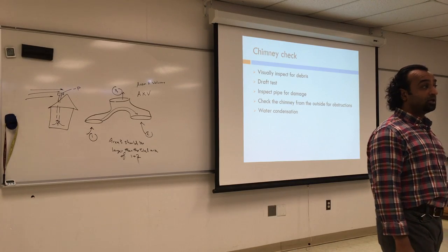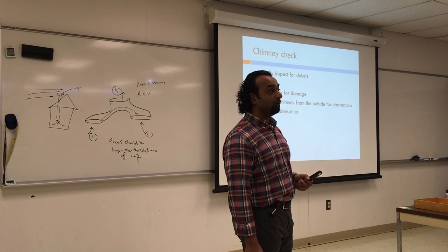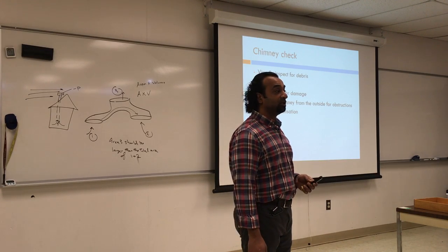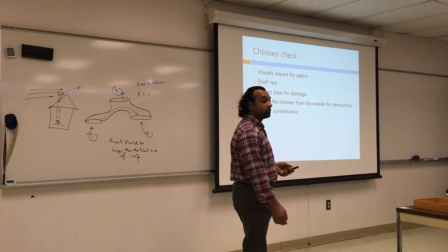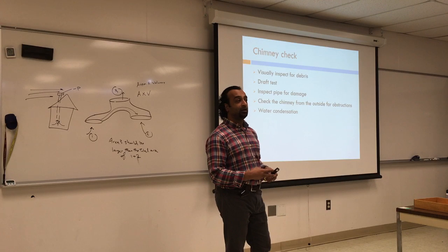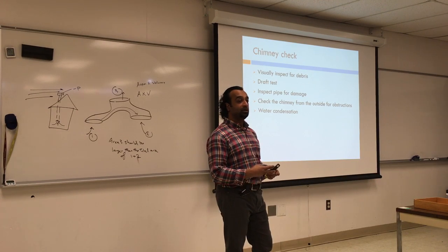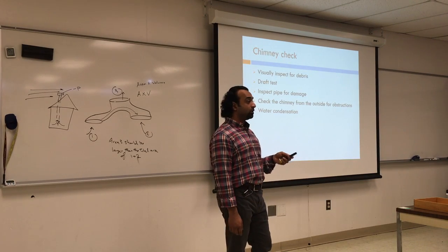Yeah, I was just about to. Backdraft, condensation, and that's something you don't want. So it's not necessarily always rain, sometimes it's condensation from your combustion, because what are the 3 things you get out of combustion as an output? Heat, carbon dioxide, and water. So there's water, and there are some other stuff dissolved in the water, so you're going to condensate water.